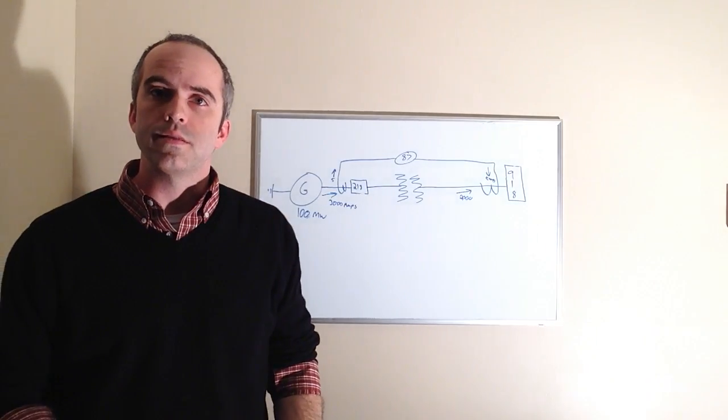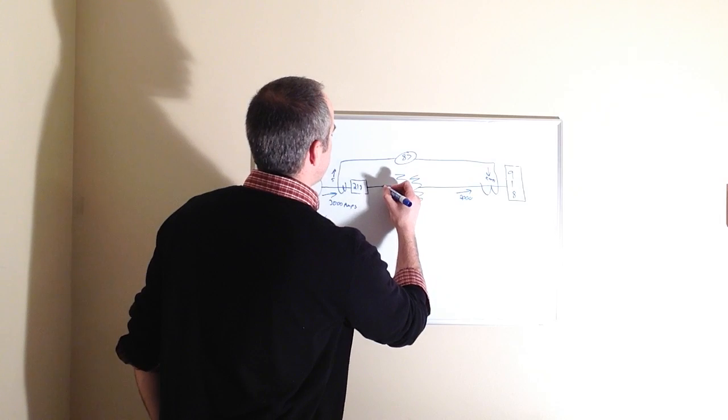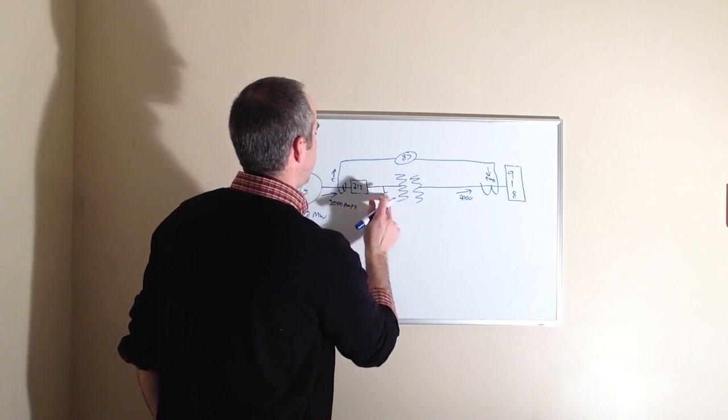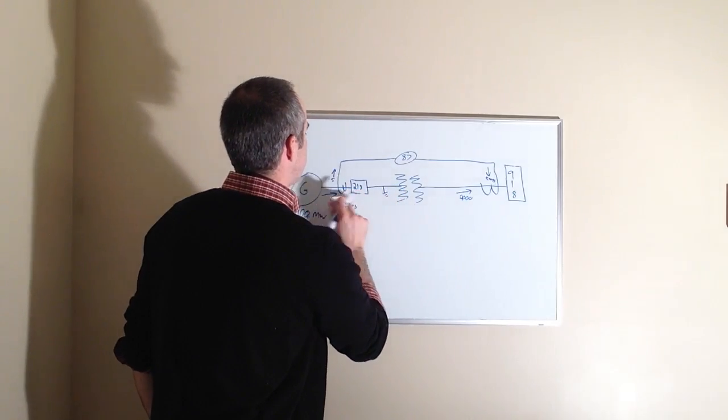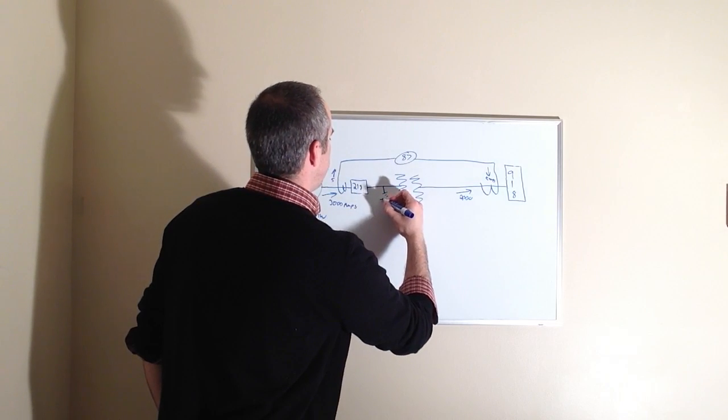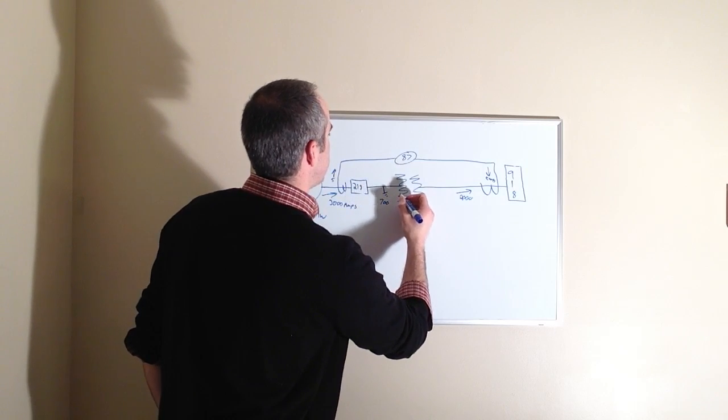We've got 5 amps here, it's calling for 5 amps here, everything's happy and balanced. Now let's put a fault to this and see how it works. Let's say we have a piece of buswork goes to ground here. So we've got 2,000 amps going here feeding the fault, or 2,000 amps going this way. Let's say we lose 700 amps here, so that leaves us 1,300 amps going here.